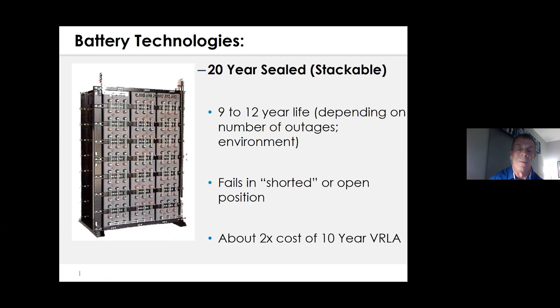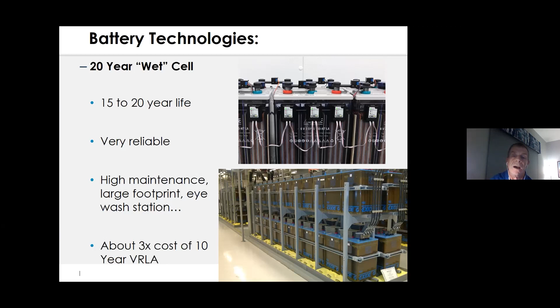And then finally, you have the wet cell batteries. Again, extremely reliable, a little bit messy to handle. They're high maintenance. You need eye wash stations, body showers, and desiccants down the bottom, these sandbags that will absorb should anything leak. And they cost about 3 or 4 times more than the 10-year batteries. You will get more life out of them, but again, all your safety measures that you have to have in place will make up for that.